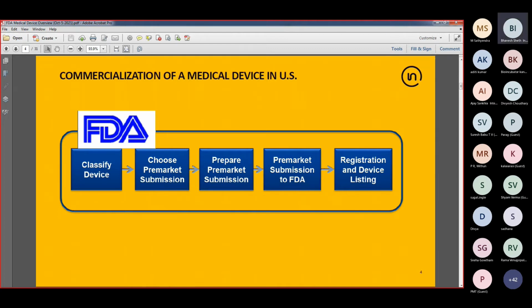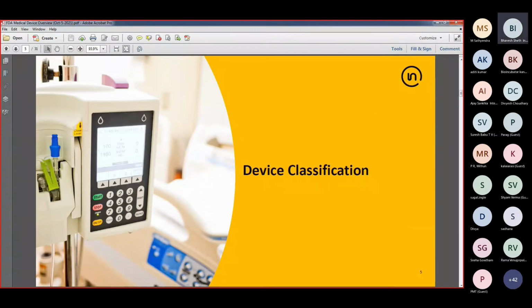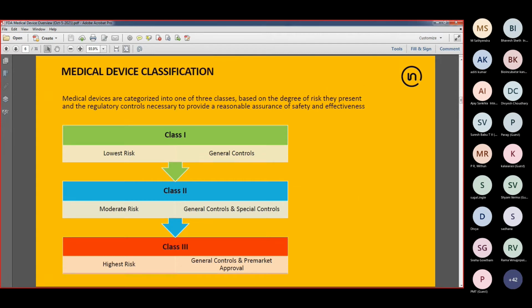Preparation of pre-market submission also includes the step of performing the necessary testing. We'll get into that a little bit later. So we'll start with device classification. The US FDA categorizes medical devices into one of the 3 classes based on the degree of risk that they present and the regulatory controls that are necessary to provide a reasonable assurance to the patient, to the user, about safety and effectiveness. So we have a class 1 category, class 2, and class 3.